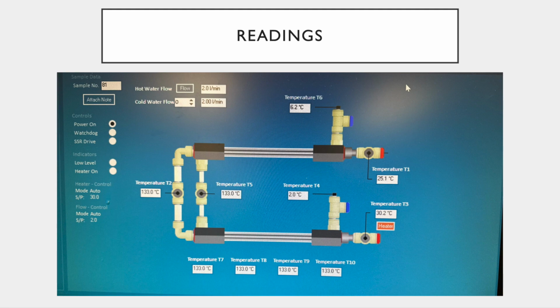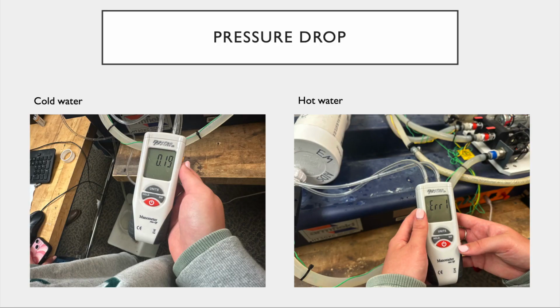After letting the system run, the cold water inlet temperature was recorded as 2 degrees Celsius and the cold water outlet was 6.2 degrees Celsius. The hot water inlet was 30.2 degrees Celsius and the hot water outlet was 25.1 degrees. The cold water pressure drop was found to be 0.1 kPa, however the hot water pressure drop was too high so could not be recorded.